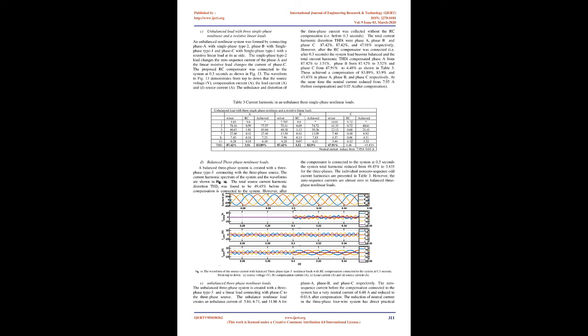B. Balanced three single-phase nonlinear loads with compensation. Fig 11 depicts the proposed control connected to the system with balanced three single-phase type 1 loads. The waveforms in Fig 11 showed that the source current is compensated from the current distortion caused by the nonlinear load of single-phase type 1. Moreover, the current magnitude of the phases was reduced from 7.52 to 7.49 A, and the neutral current was reduced to almost zero. The total source current harmonic distortion, THDi, was reduced from 80.32% to 4.2% as shown in Fig 12. Fig 11, the waveform of the source current with balanced three single-phase type 1 nonlinear loads with RC compensation. Fig 12, harmonic spectrum of the balanced three single-phase type 1 nonlinear loads with RC compensator.